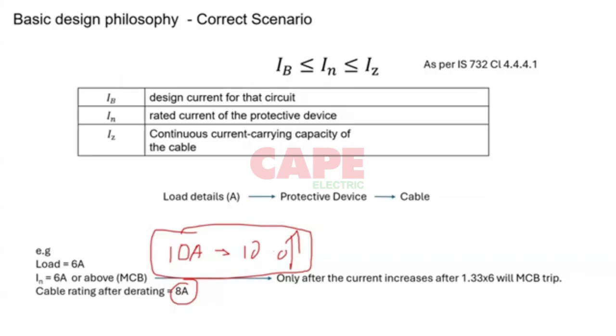But obviously, sometimes there are some practical concerns at the sites also. We can't ignore it, because sometimes clients can come and say that they want to increase the load after a certain point. It's a valid point, but even if you want to increase the load after a certain time, it is better to plan in such a way that the protective device size is always designed to the load current in that scenario.